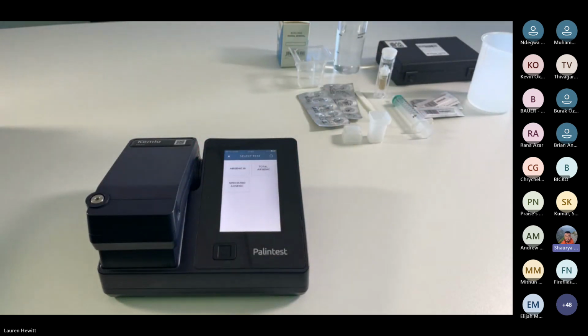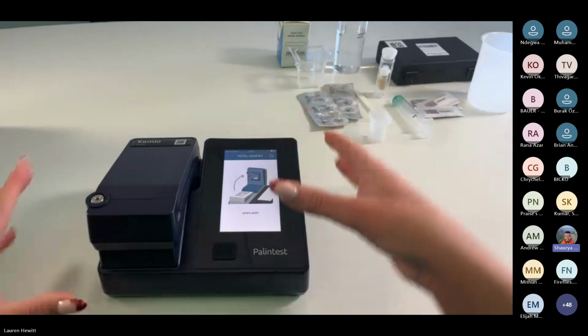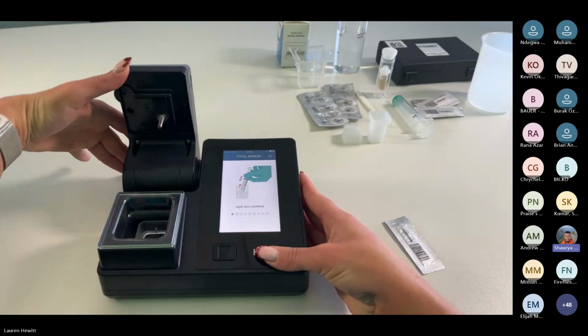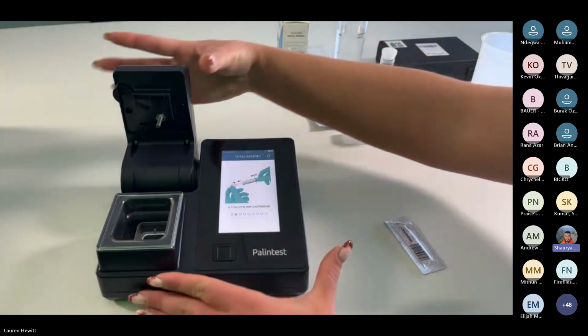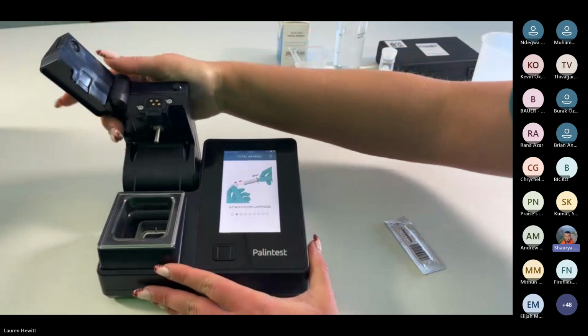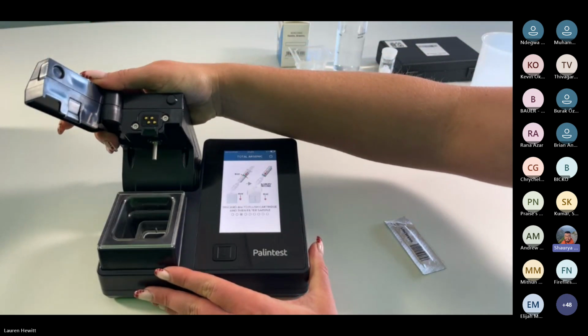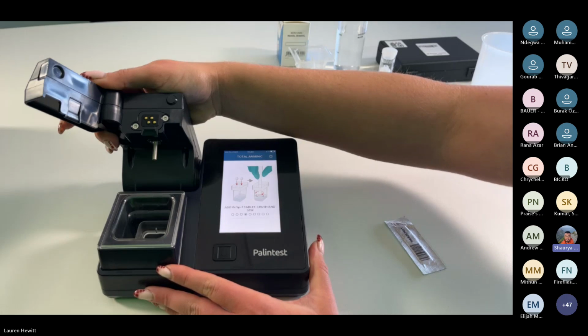And as you can see, it will give the option for which test to perform. So as Sharia mentioned, there are different forms of arsenic in the water, and the Kemio can test for those different forms. But today we're going to concentrate on total arsenic. So that's the test that we're going to select. Now, a really good benefit to Kemio, as you can see now, is our on-screen instructions. So anybody unfamiliar with the device can just follow the screen instructions step by step and ensure that they are doing the test correctly. So opening the arm. While we're here, I just want to show where the connection is made. Inside of the Kemio here is the contact pad, and this is why it's really important, when we're talking about the correct way to insert the sensor, that it only goes in one way so that the correct connection is made.